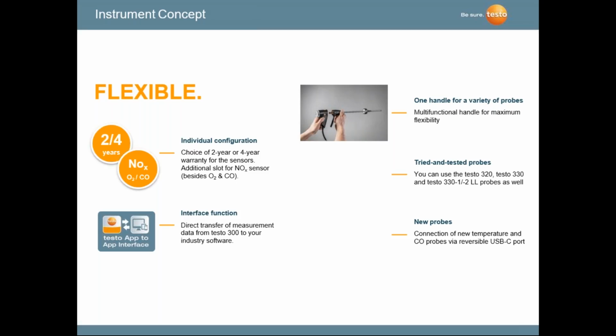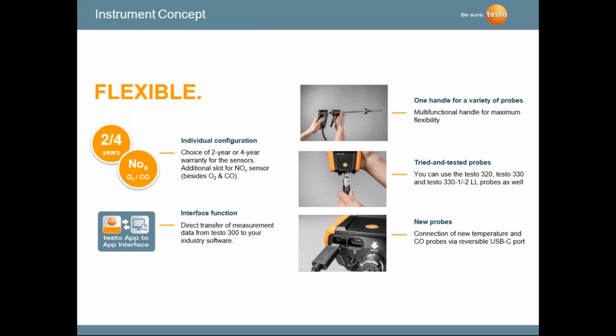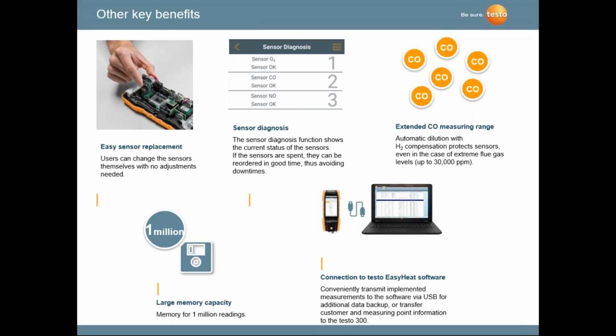One of the things that's nice is the flexibility of the probes. You got a probe, you got a 9-foot hose, you got a 13 to 14-inch probe tube that is interchangeable. It's a quick connection on the bottom of the instrument, which ties in the thermocouple, the draft hose, and the flue gas hose. And of course, you can attach different probes to the bottom of the instrument. Say, for instance, if you want to do a primary air temperature using a different type of temperature probe. Interchangeable sensors, sensor diagnostics. We even have a range that goes up to 30,000 ppm on the CO, which I'll get into a little bit later. All this comes complete with a software package.